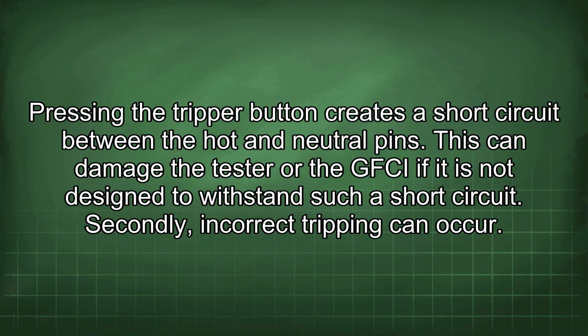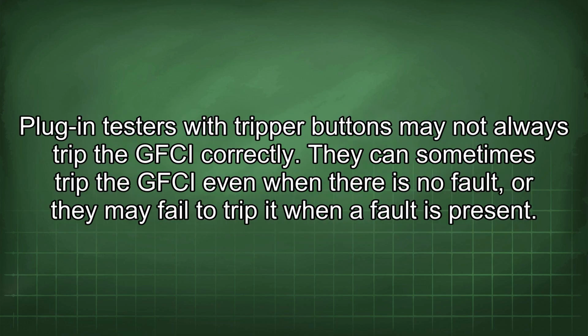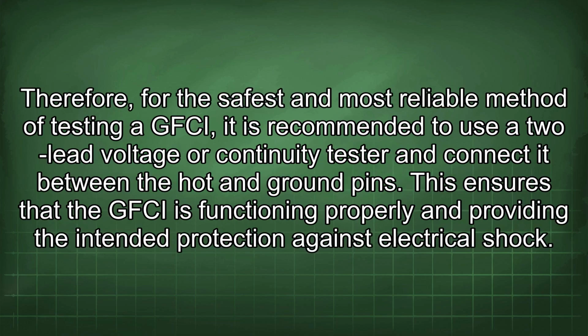Secondly, incorrect tripping can occur. Plug-in testers with tripper buttons may not always trip the GFCI correctly. They can sometimes trip the GFCI even when there is no fault, or they may fail to trip it when a fault is present. Therefore, for the safest and most reliable method of testing a GFCI, it is recommended to use a 2-lead voltage or continuity tester connected between the hot and ground pins. This ensures that the GFCI is functioning properly and providing the intended protection against electrical shock.